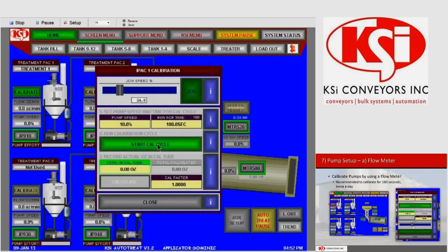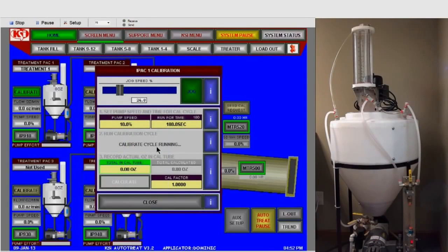Once we have that set up, we're going to go ahead and press start cal cycle. At this time, our pump is going to begin running, and we'll see our run for time here counting down from 180 to 0. You can see in this window our total calculated is climbing. It's at 4.74, and that is the flow meter accumulating, totalizing how much liquid has run through it. Once this 180 seconds is complete, we're going to read how much liquid was in the cal tube, and we're going to enter that value right here.